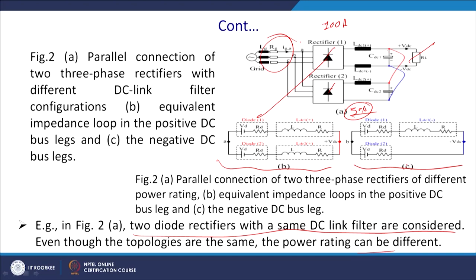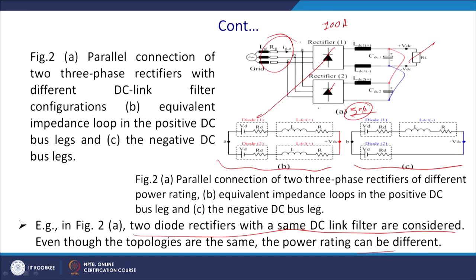The inductance values of the filters are determined according to the base impedance in per unit. Therefore, inductance values change with respect to the power level — generally, inductance is specified as 5% in per-unit value. Once you change the power handling capability, your design constraints also change. In figures 2b and 2c, the positive or negative DC links of rectifier 1 and 2 are connected to the same terminal, with the major issue being that DC output current depends on the resistance of the DC link, mainly the diode and DC link choke.